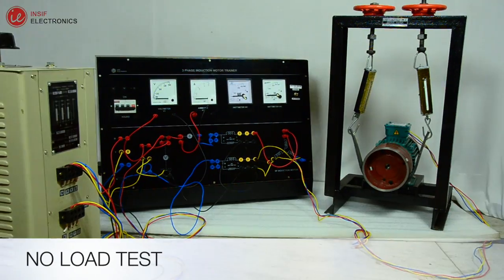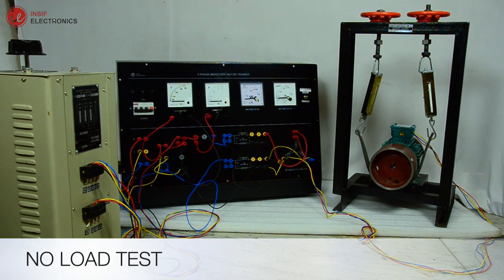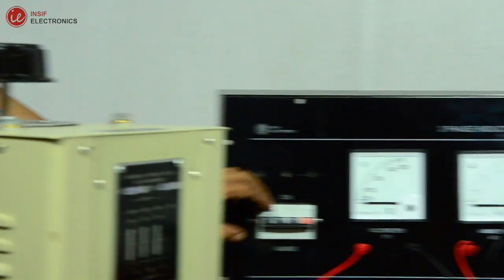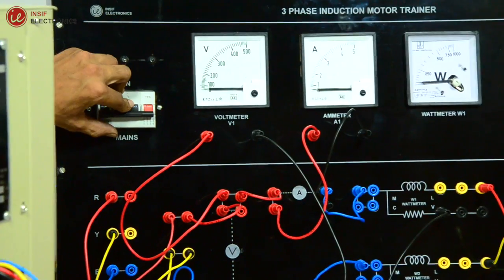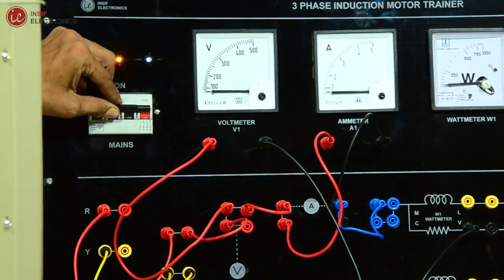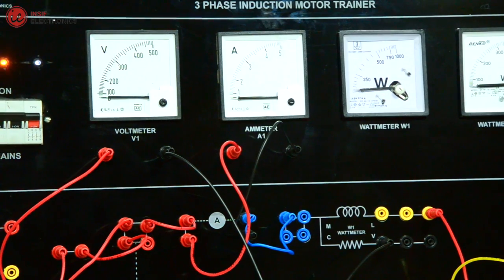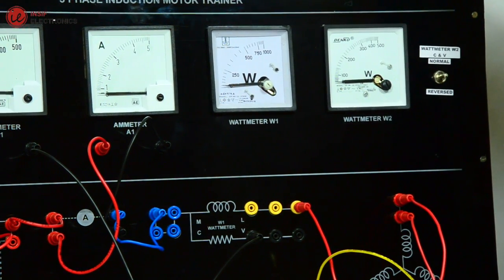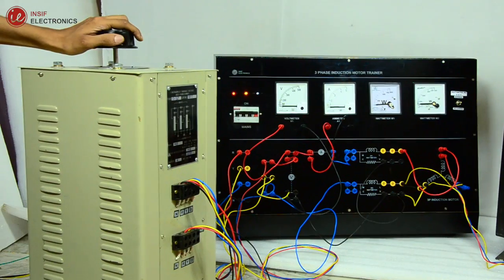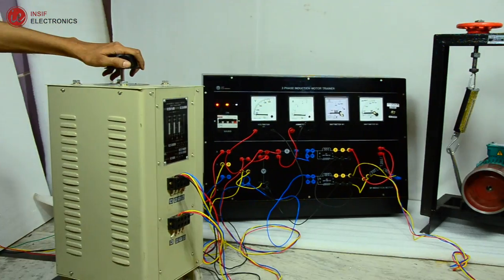Now let's start the no load test. For that, make sure the variac should be at minimum position and now switch on the panel by pulling up the MCB. Make sure all the pointers in the meters should be at zero position and loosen the load on motor. There should not be any load on motor as we are performing no load test.